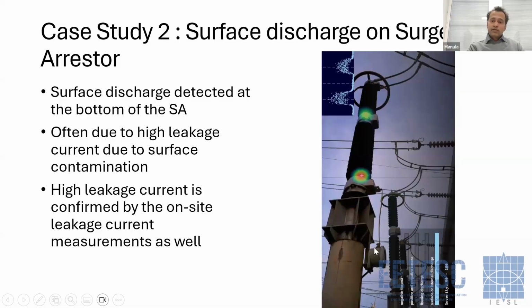So usually these surge arrestors are equipped with leakage current meters so that we can cross-check whether there is a leakage current, or if it is higher than the recommended level, it is always recommended to, for example, wash the surface and take whatever remedial action they can. So here this snapshot is showing these two locations. That is very important. Both of the locations, that is one of the features of these acoustic cameras. It would not only show the highest sound source but also show the other sound sources as well. So you can have single sound source as well as multi sound source modes, so that from a single frame you can detect different sound sources.